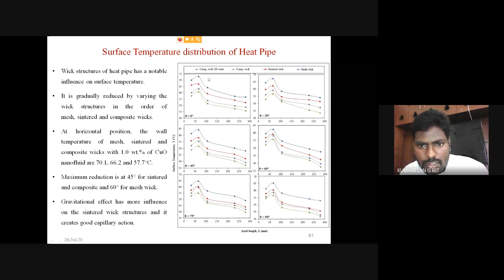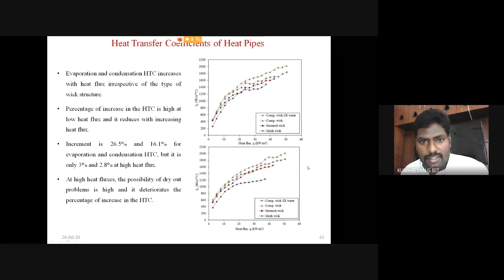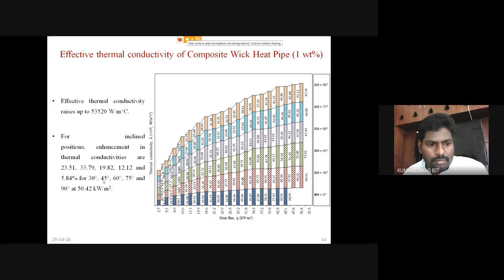Okay, then HTC of heat pipes operating with a composite wick, that means composite wick and 1 weight percentage of CuO nanofluids, registered the highest HTC value at the evaporator as well as in the condenser section. Then next, effective thermal conductivity comparison of composite wick heat pipes. The effective thermal conductivity of the heat pipe rises up to 53,520 watt per meter degree Celsius for the heat pipe operating with a combined sintered and mesh wick at 1 weight percentage and 45 degree inclination angle.